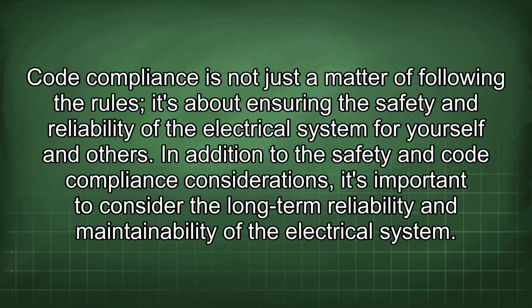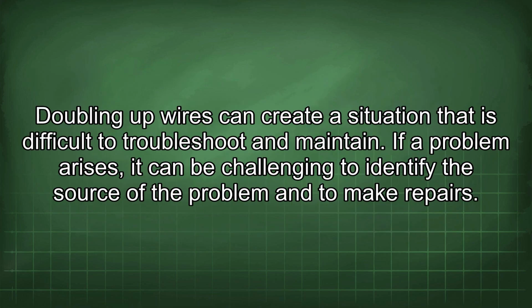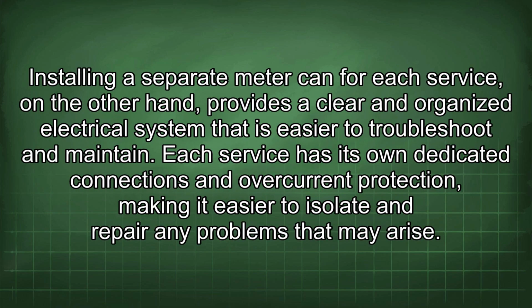In addition to the safety and code compliance considerations, it's important to consider the long-term reliability and maintainability of the electrical system. Doubling up wires can create a situation that is difficult to troubleshoot and maintain. If a problem arises, it can be challenging to identify the source of the problem and to make repairs. Installing a separate meter can for each service, on the other hand, provides a clear and organized electrical system that is easier to troubleshoot and maintain. Each service has its own dedicated connections and overcurrent protection, making it easier to isolate and repair any problems that may arise.